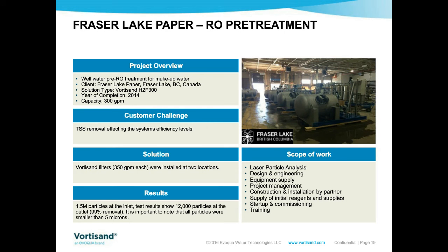Finally, a different type of application for the CROSSFLOW MICROSAND filter. Given that it performs very well at removing very fine particles, it was selected at Fraser Lake Paper Mills as pre-RO treatment in 2014, and shortly after we completed a very thorough R&D program where we developed the horizontal filter product line that you see in the picture. We supplied filters to treat well water, and well water contained high loading of iron and other calcium and other ions that are very detrimental to membrane, reverse osmosis membrane.